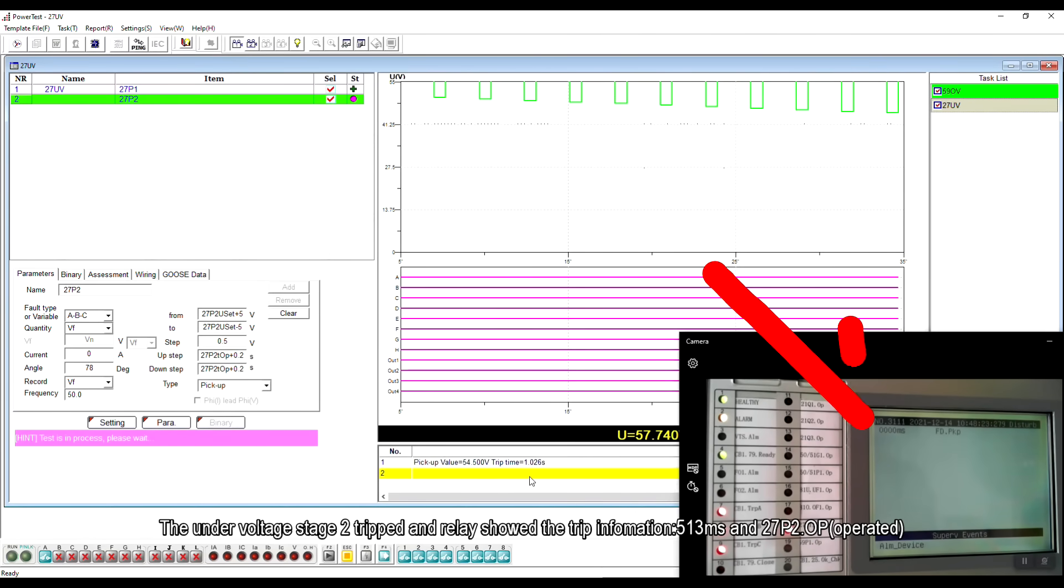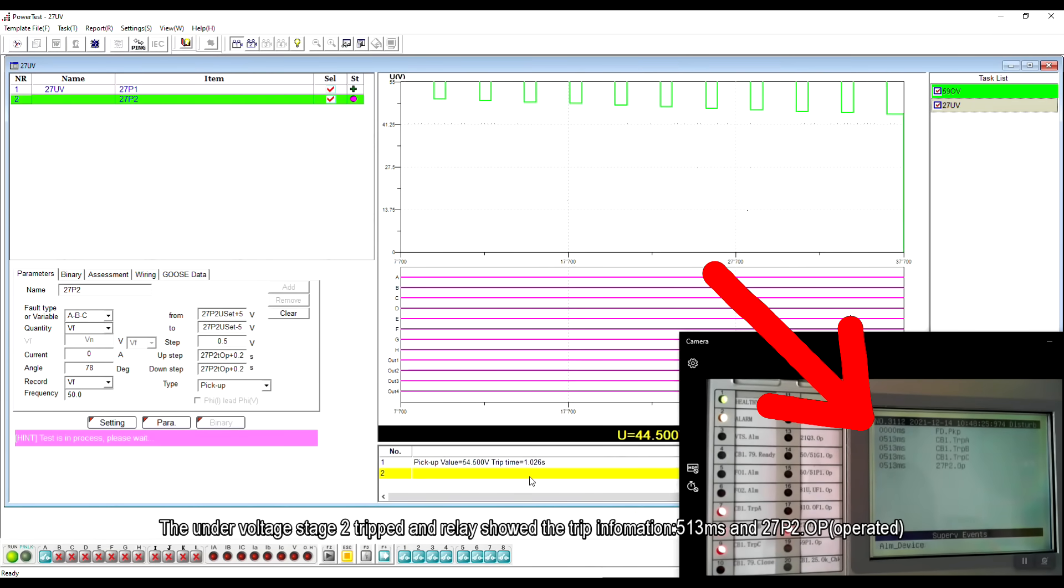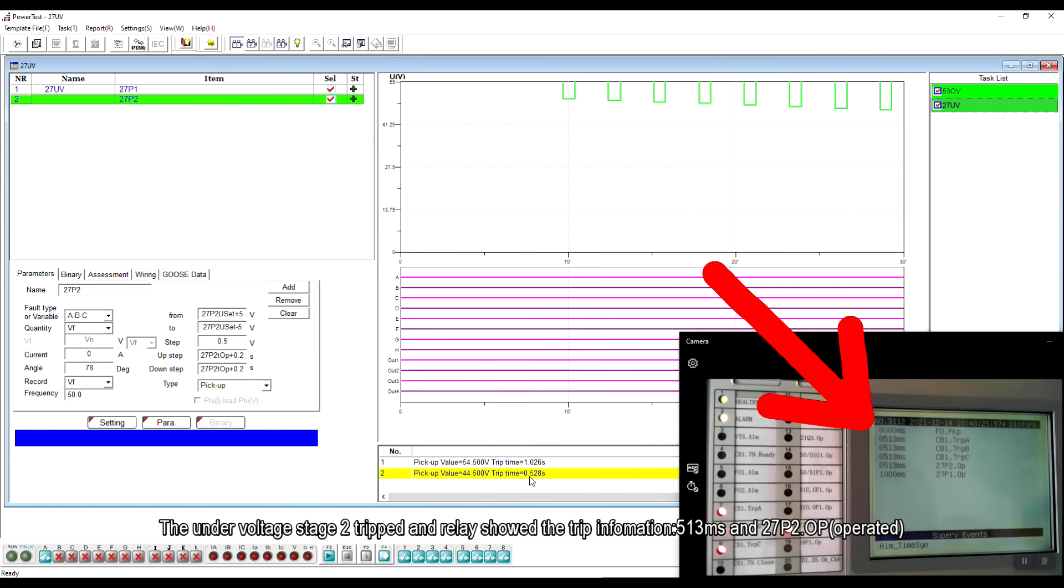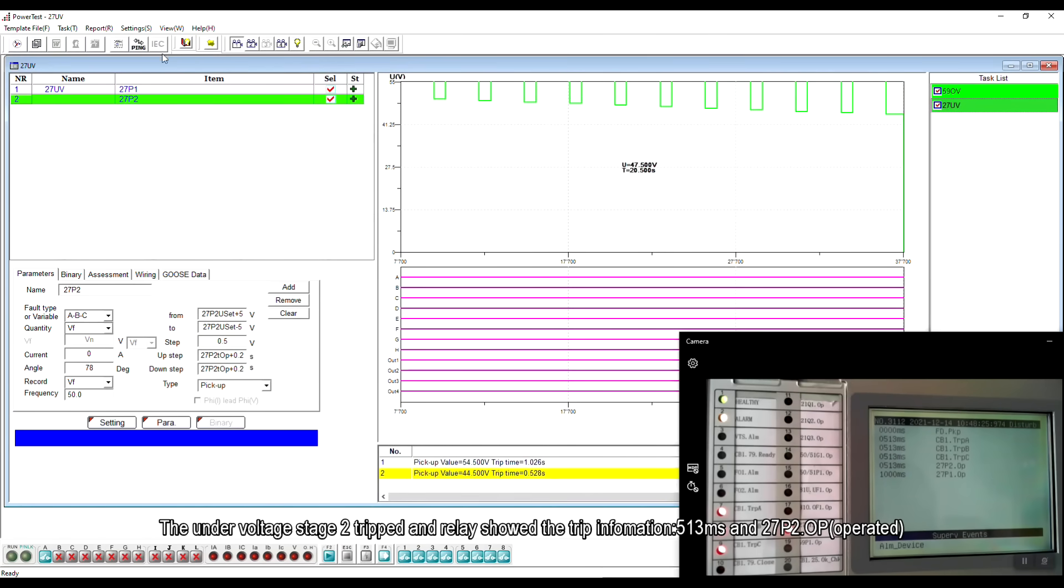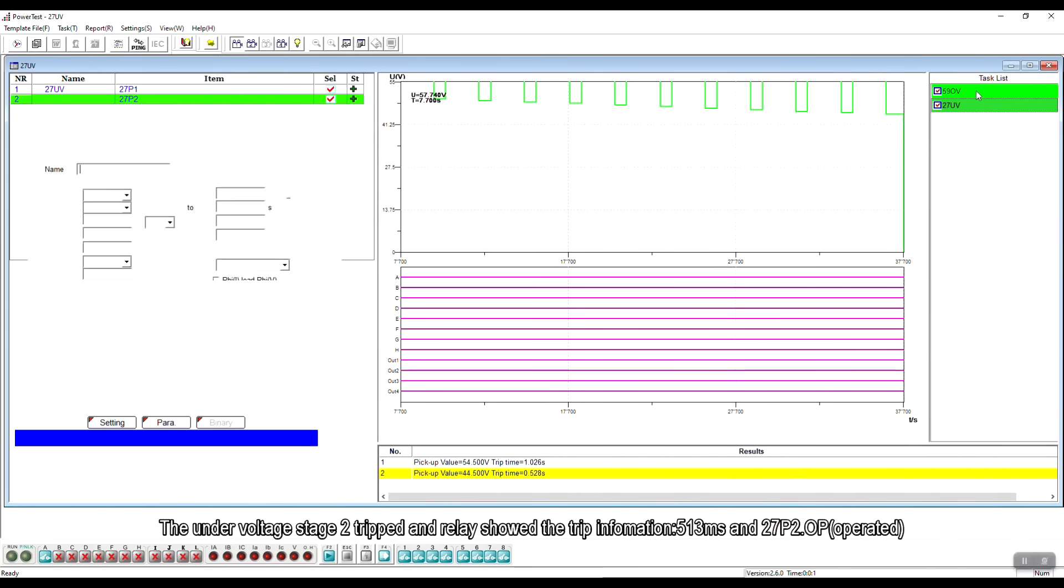The under-voltage stage 2 tripped and the relay showed the trip information, 513ms and 27P2 operated.